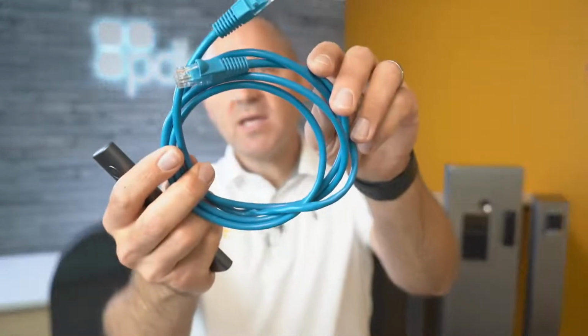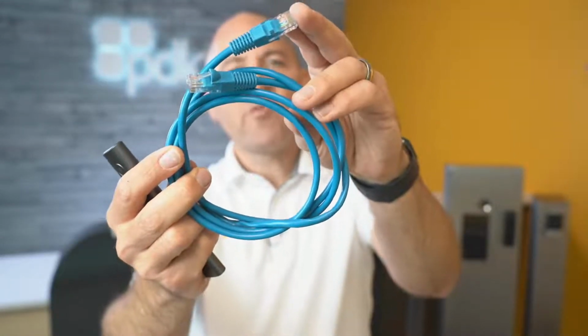Another thing that's very important when plugging in Cat 5, Cat 6, or whatever it may be, is knowing that this type of wire has a specific run length. You can't just run Cat 5 or Cat 6 as far as you want. You're going to get about 328 feet, which is the run length of Cat 5 and Cat 6, and that can vary based on a few things. But if you're running greater than 328 feet, you need to plug into another device, like another switch, that will get you another 300 and some odd feet.